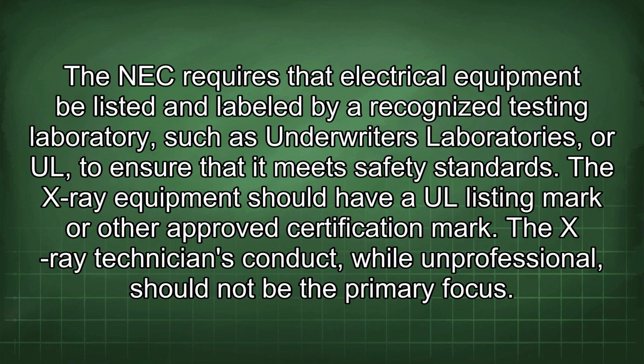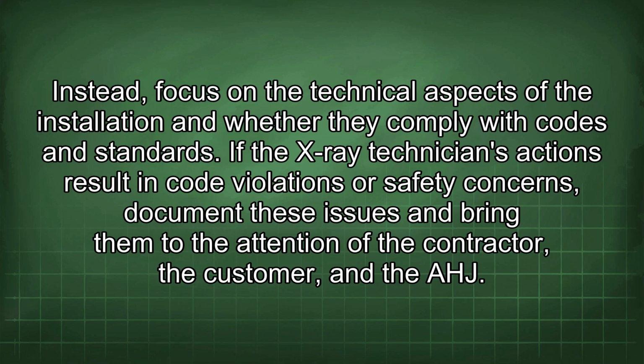The NEC requires that electrical equipment be listed and labeled by a recognized testing laboratory, such as Underwriters Laboratories, or UL, to ensure that it meets safety standards. The X-ray equipment should have a UL listing mark or other approved certification mark. The X-ray technician's conduct, while unprofessional, should not be the primary focus. Instead, focus on the technical aspects of the installation and whether they comply with codes and standards. If the X-ray technician's actions result in code violations or safety concerns, document these issues and bring them to the attention of the contractor, the customer, and the AHJ.